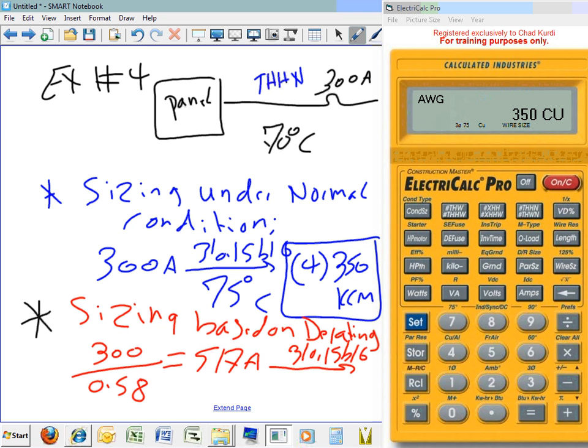310.15(B)(16). Under which column and why now? 90. We're derating, under the 90-degree column. And now from this, who's going to be my friend to give me the answer? 517. Look, did you see the temperature that we gave you? 70. You know what 70 is? 70 is as close to the Lord's hell as you can get. Have you been in 70? Anybody encountered 70? How much? 700? Yep. Did you guys come up with 700? 517, yeah, 520, 700. Thank you. So my conductor should be 4 conductors, 700 kcmil.